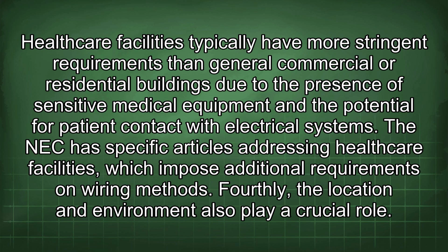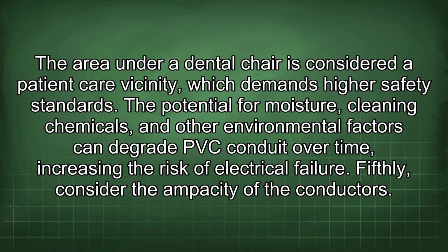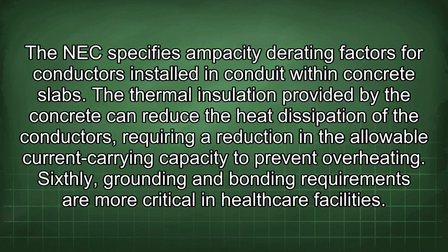Fourthly, the location and environment also play a crucial role. The area under a dental chair is considered a patient care vicinity, which demands higher safety standards. The potential for moisture, cleaning chemicals, and other environmental factors can degrade PVC conduit over time, increasing the risk of electrical failure. Fifthly, consider the ampacity of the conductors. The NEC specifies ampacity derating factors for conductors installed in conduit within concrete slabs. The thermal insulation provided by the concrete can reduce the heat dissipation of the conductors, requiring a reduction in the allowable current carrying capacity to prevent overheating.